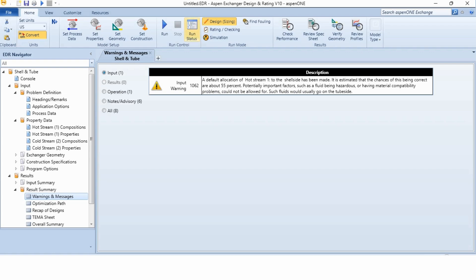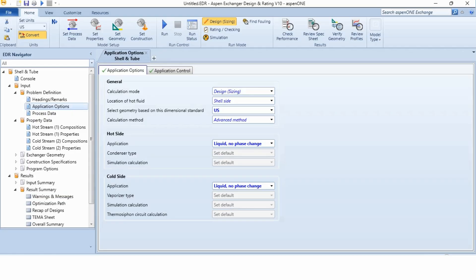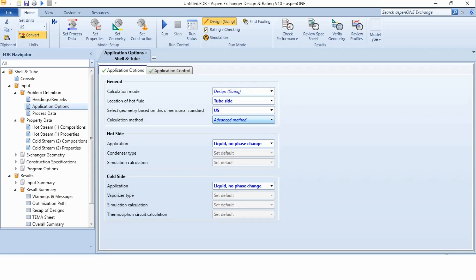It is estimated by the Aspen that chances of this being correct are about 55%. Potentially important factors such as fluid being hazardous, material compatibility issues could be involved. So, this is the first advisory which has been issued to us by the Aspen based on the properties of the fluid that you need to move it to the tube side. So, how we can move it? We can go to the application options and here, location of hot fluid, we can change it to tube side.